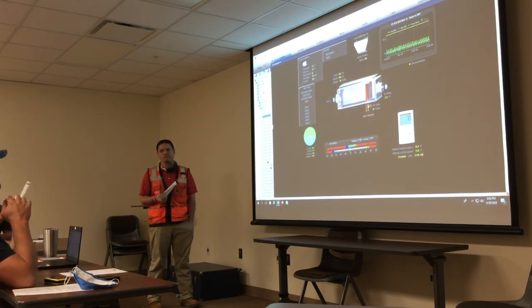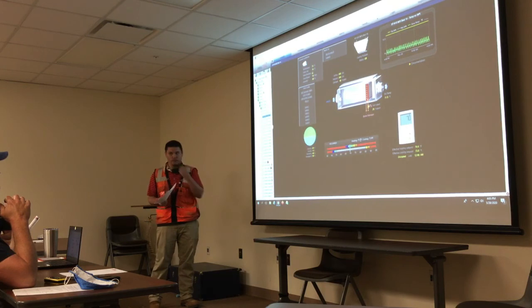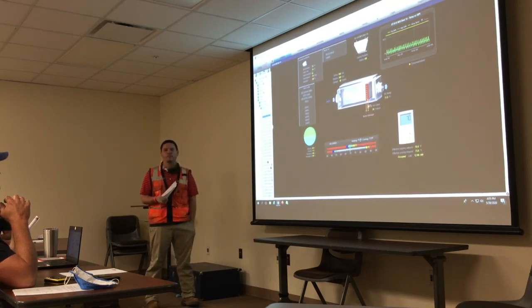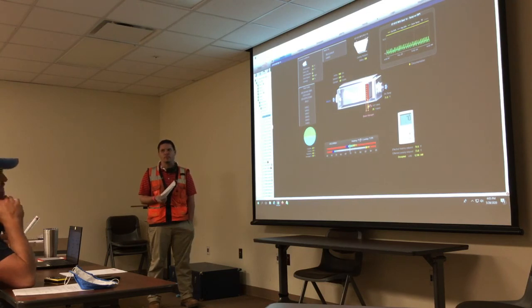Need to tighten that band up. If they're cold, then the way I look at it is you can tighten that band up. I don't recommend anything less than 2 degrees or you're going to get it going back and forth. But if they're cold, what you're doing is pushing the whole band up. So if right now in that space it's 70 degrees and they want to be warmer, you push that up 2 degrees and it's going to heat to 72. So they're going to warm up.